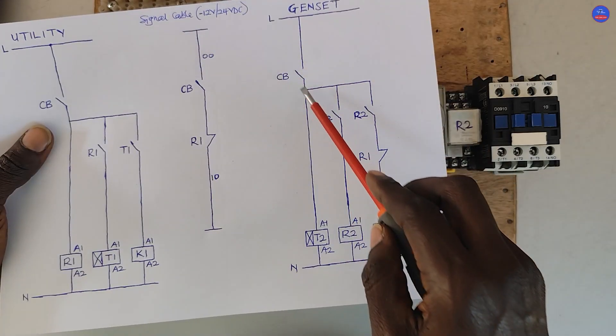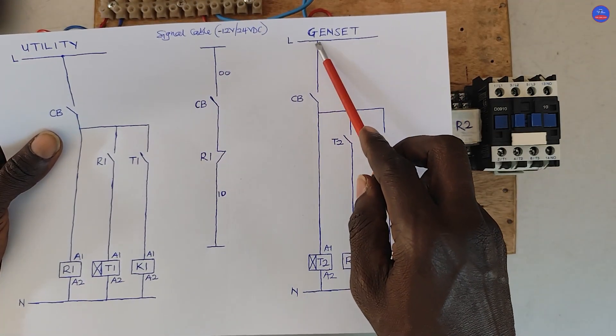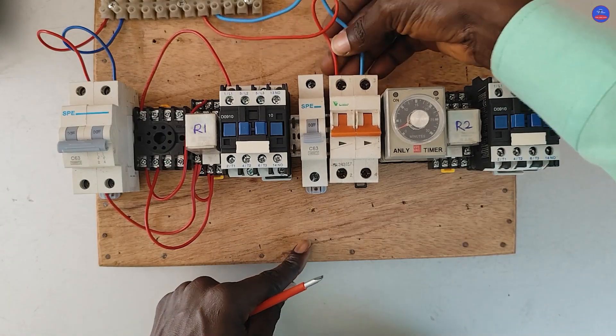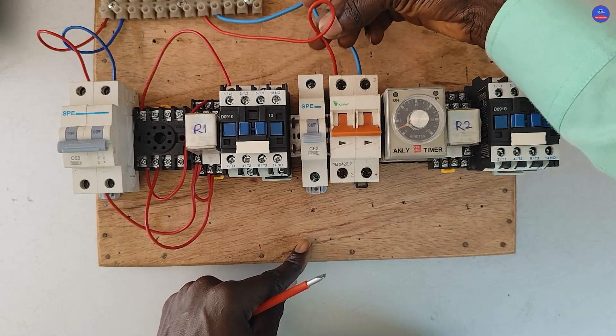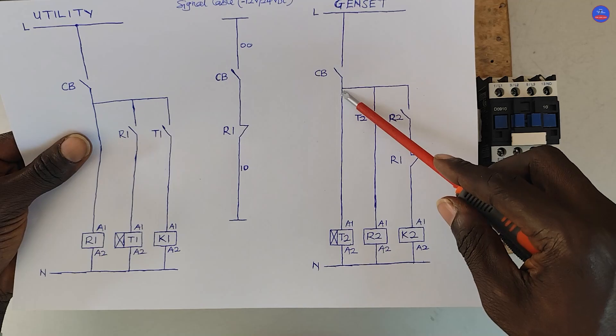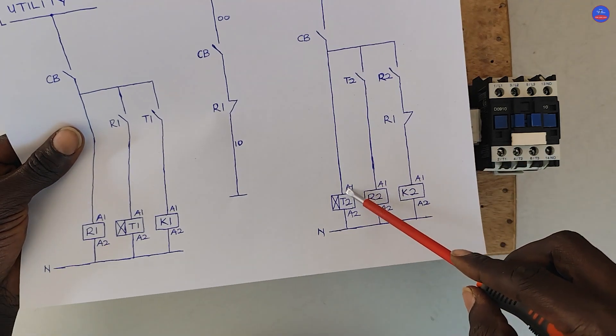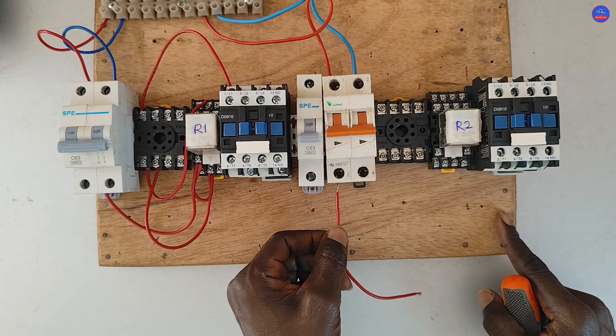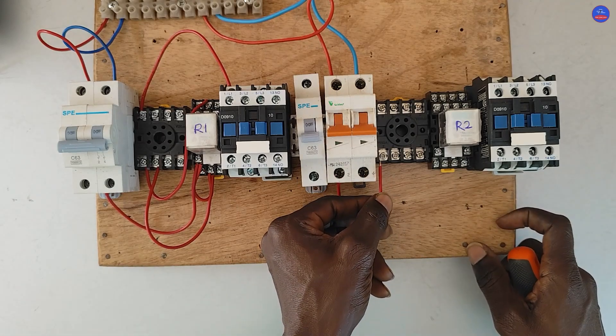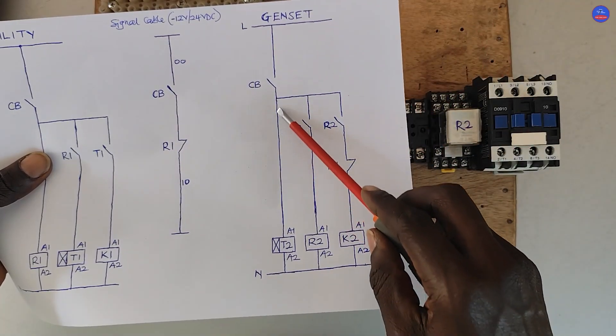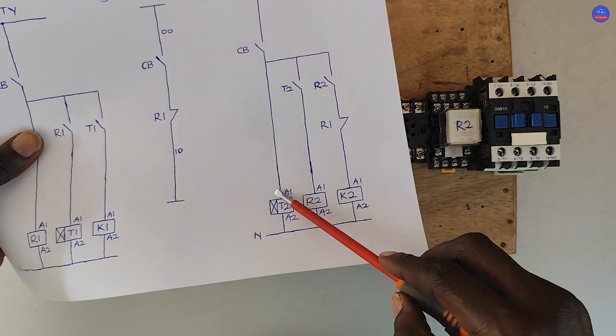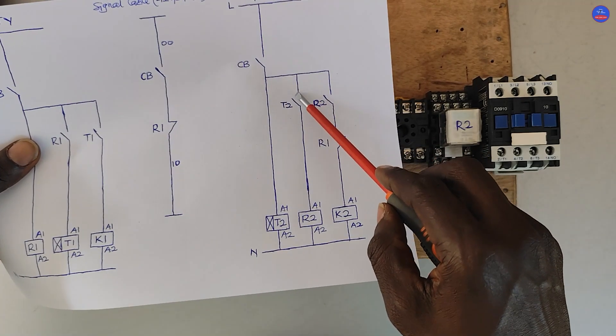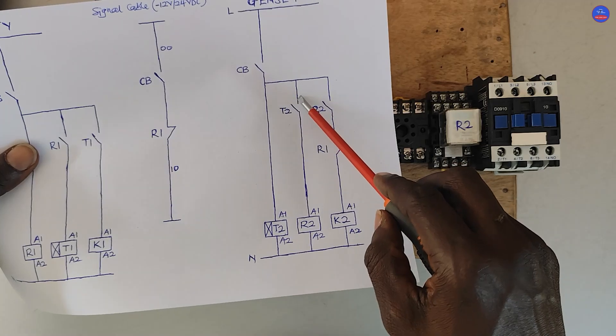We are moving to the generator side. We tap from the generator output to one side of the breaker — this is the generator breaker, so this is the live. From the output of the breaker, it goes to terminal A1 on the timer, which is terminal number 7. We can equally tap from this side or this side. So we tap from A1 to one side of the open contact on the timer, which is terminal number 8.